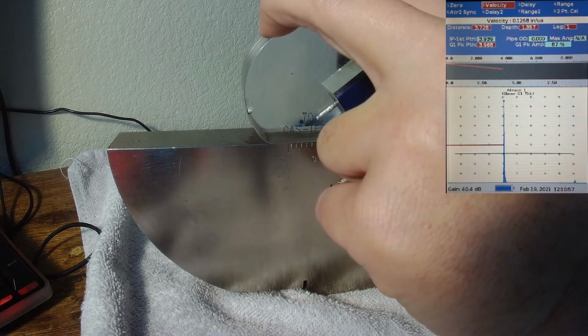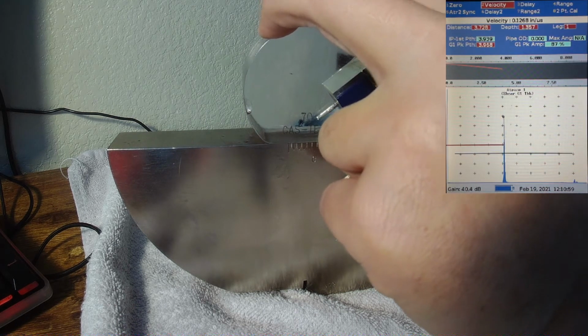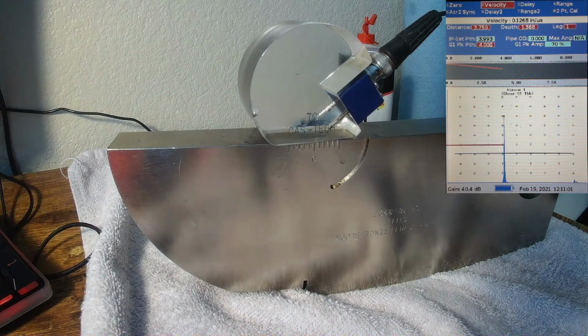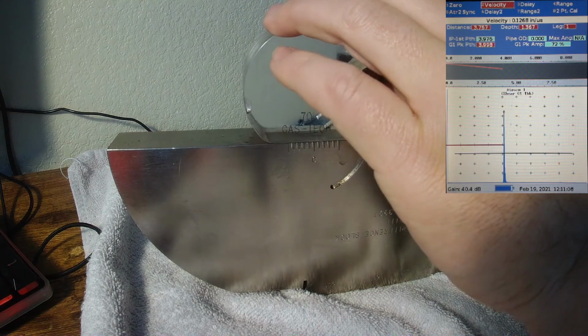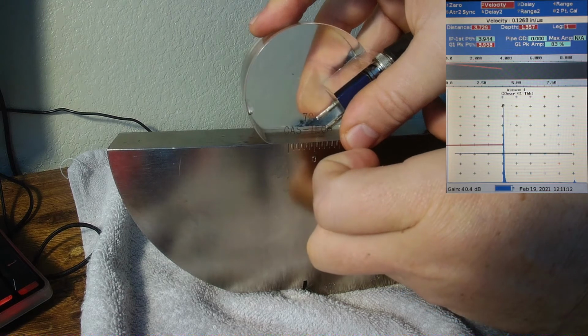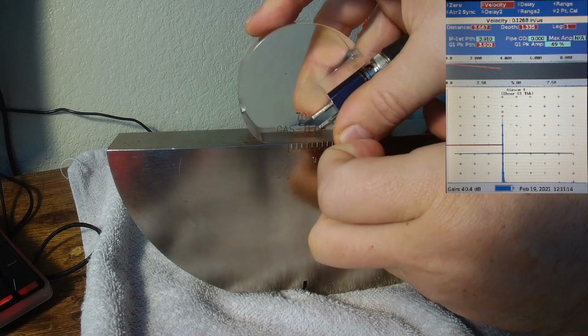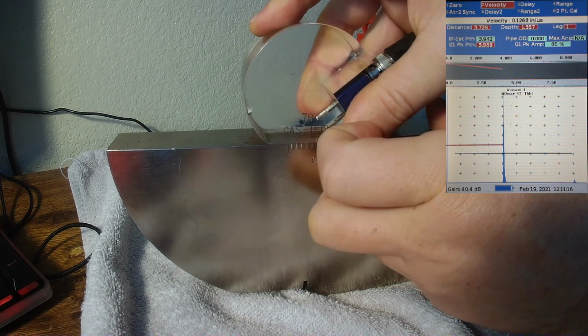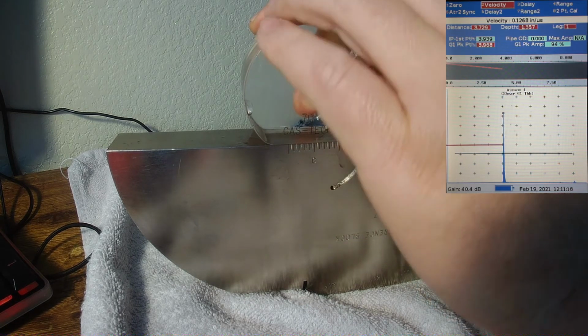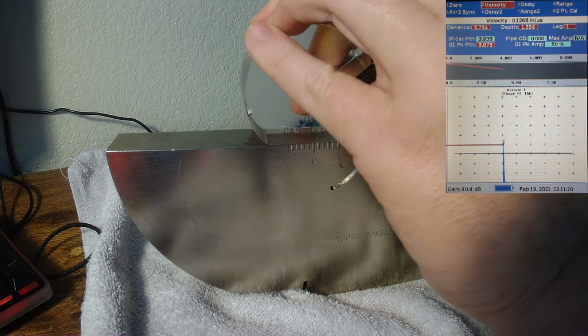And you can look at your velocity table. So the standard velocity for mild steel is 0.13 for shear. But then you can put that in there and adjust it like what we're doing right now in calibration to get the exact amount of velocity that you need.